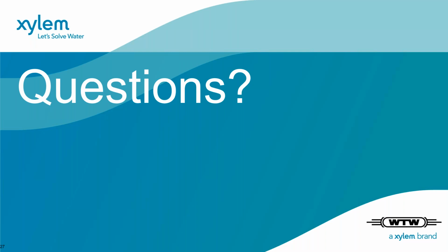Great. Just quickly going back to the module question that you addressed earlier. Sorry, how many NH4 modules? One. I get the question regarding Trescon, our old analyzer, where you have 3 modules for 3 different parameters in one analyzer. The Alyza has only one ammonium module, but you can measure up to 2 sample streams. That means you can sample from 2 different locations and measure both in one analyzer, but only one ammonium module inside.